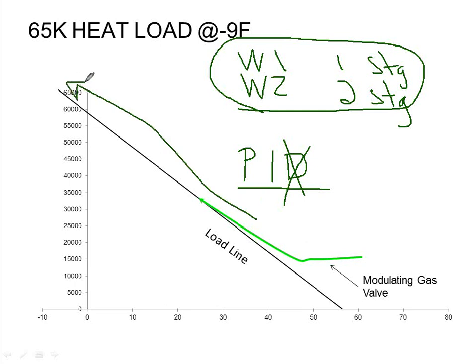But then as I get closer to 85, I get to 78, 79, 80, 81, I start backing off that gas valve. And I want to land exactly on 85. I don't want to stop short of 85. I don't want to overshoot 85. I want to land right on 85 miles an hour. So as I get closer, I back off the gas pedal. This furnace is going to do the exact same thing. As I get closer to the desired temperature set point, I'm going to back off the gas pedal, and I'm going to provide you less and less gas and only give you enough gas to heat your house for your heat loss at that moment. Excuse me. Just like your car is only going to give you enough gas to maintain the 85 mile an hour cruise control set point. No more, no less.